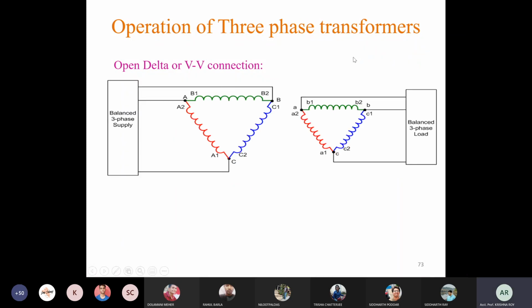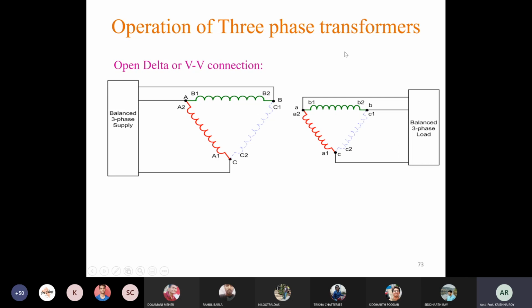So this is the normal or healthy delta delta connection, we can see. So if we remove one of the phases, suppose this C phase transformer is removed from this delta delta connection, then this open delta connection will form. Okay, so here we can see from the primary side that we are still supplying a three phase balanced supply. See, this is the three phase balanced supply which is still connected to the primary side.